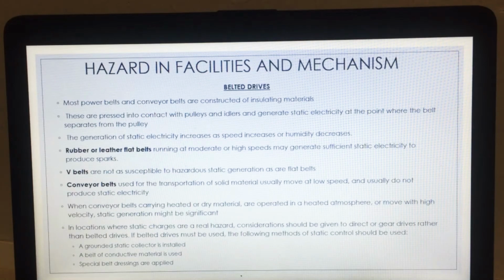Conveyor belts used for the transportation of solid material usually move at low speed and usually do not produce static electricity. When conveyor belts carrying heated or dry materials are operated in a heated atmosphere or move with high velocity, static generation might be significant. In locations where static charges are a real hazard, consideration should be given to direct or gear drive rather than belted drive. If belt drive must be used, the following methods of static control should be used. Firstly, a grounded static control collector is installed. Second, a belt of conductive material is used. And lastly, special belt dressings are applied.